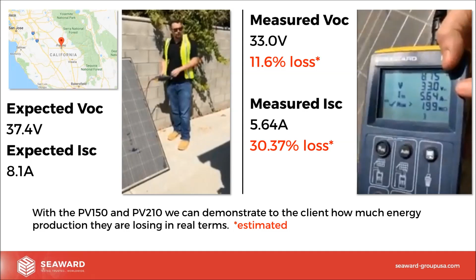So we can tell now with the context of our expected results that our measured results were being affected. So you can see quite clearly in the picture it's because the panel was soiled. So we would not know that, not doing a visual inspection of the panels, and we wouldn't be able to represent that to the customer if we didn't also take our irradiance and our cell temperature values. You could then go one further and take an IV curve trace at the same time and further represent this to your client.